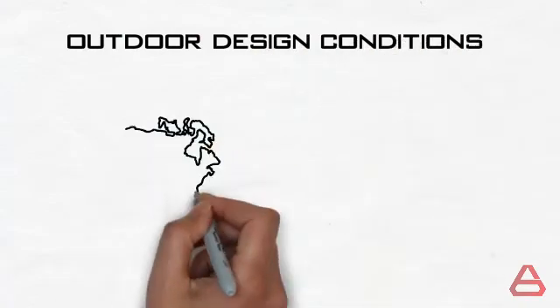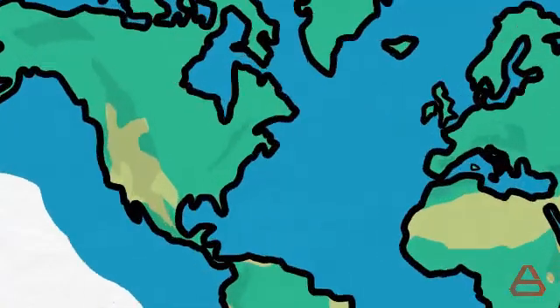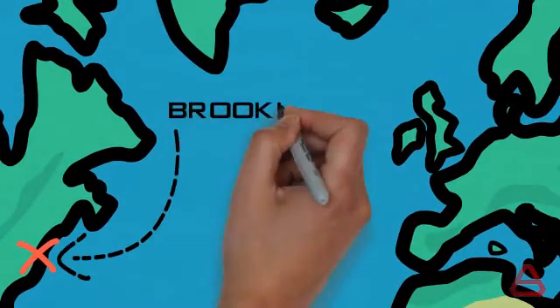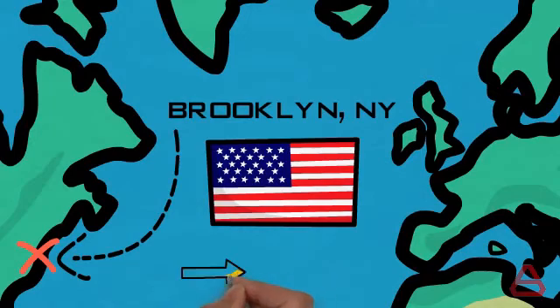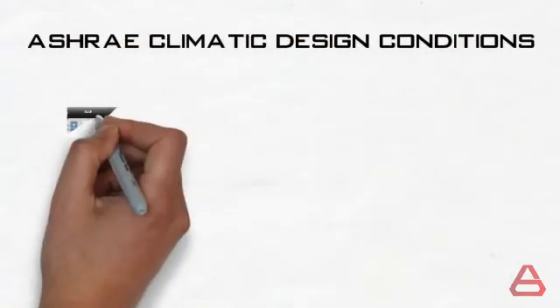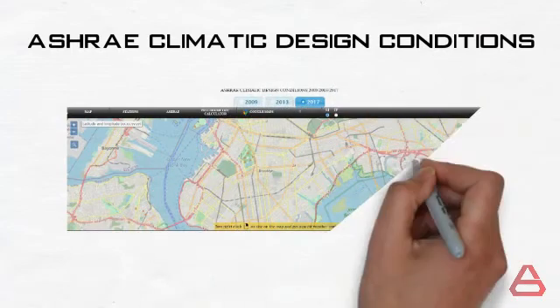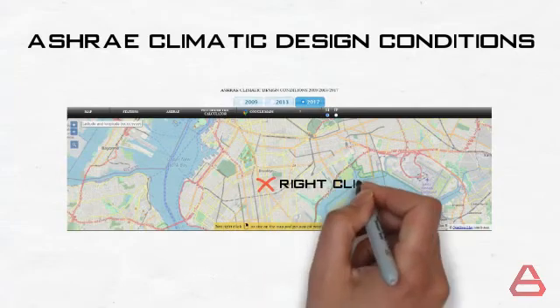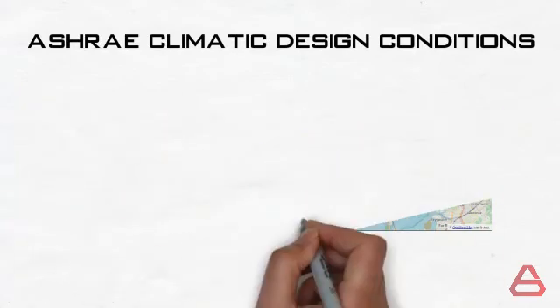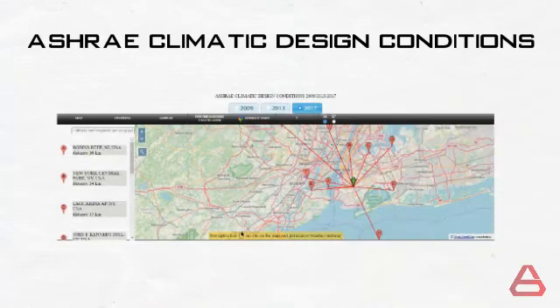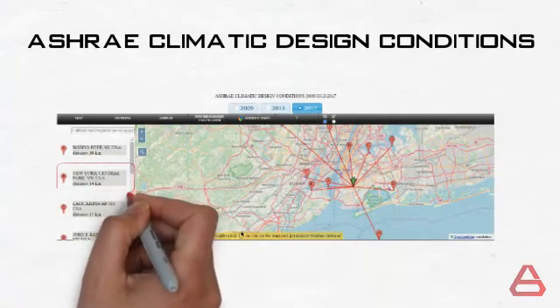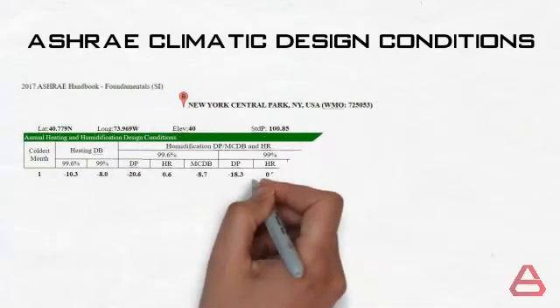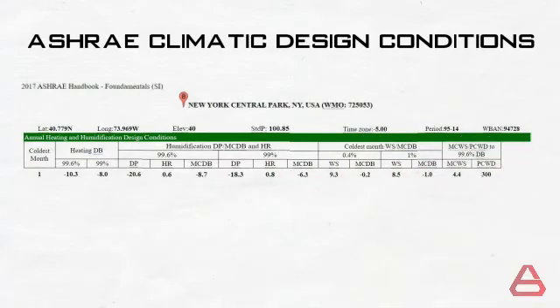To determine outdoor conditions, we need only the geographical location of the office to be studied, which we know from Sarah is Brooklyn, New York. As we learned in the previous video, let's head to the ASHRAE Climatic Design Conditions website. We locate Brooklyn on the map through simple mouse navigation, then right-click in the center of Brooklyn. Directly, a number of close weather stations appear on the left. We'll choose the central park station.